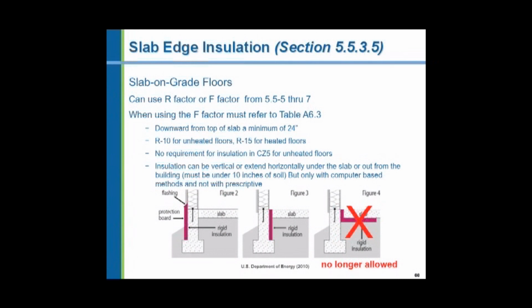They say they want it vertically in commercial, either on the inside or the outside. Now, if it's on the inside, keep in mind that we're talking about the full thickness of the perimeter insulation now. It used to be that we would have simply a thermal break, which might be a 1/2 inch wide gap filled with some kind of an asphalt mastic material. Well, now they want the full thickness of the perimeter insulation, which is at least 1.5 inches now.